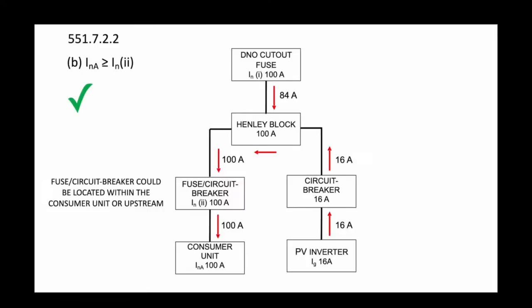Yes, this solves it, because what we need to do is supply the generator. Before we start, we need to install an overcurrent protective device upstream of the consumer unit. As you can see there, that could be a fuse or a circuit breaker. And then we also need to install the generator upstream of that fuse. So now the generator is coming through that fuse. Looking at the drawing, it's the left-hand side above the consumer unit. We've inserted a new fuse or circuit breaker rated exactly the same as the incoming DNO's cutout fuse at 100 amps. So we're not worried about selectivity on that.